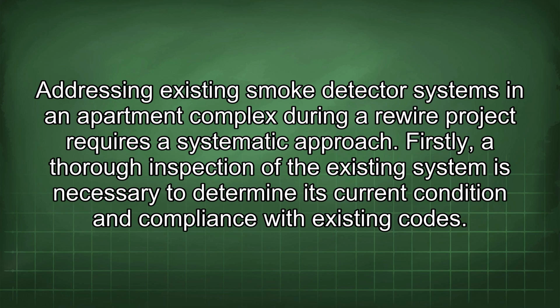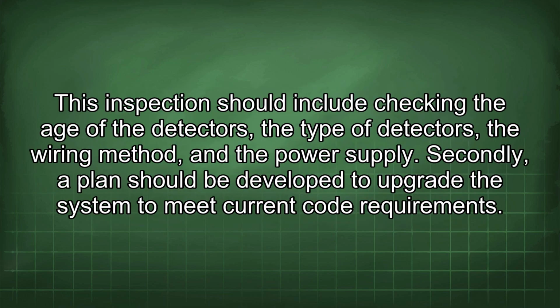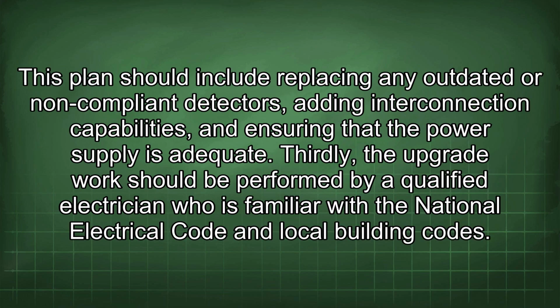Firstly, a thorough inspection of the existing system is necessary to determine its current condition and compliance with existing codes. This inspection should include checking the age of the detectors, the type of detectors, the wiring method, and the power supply. Secondly, a plan should be developed to upgrade the system to meet current code requirements.